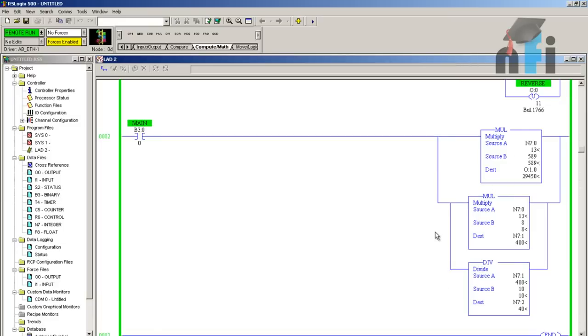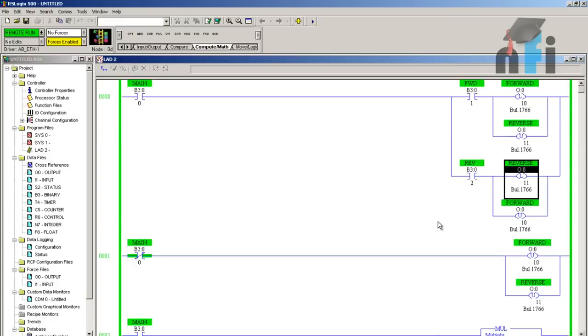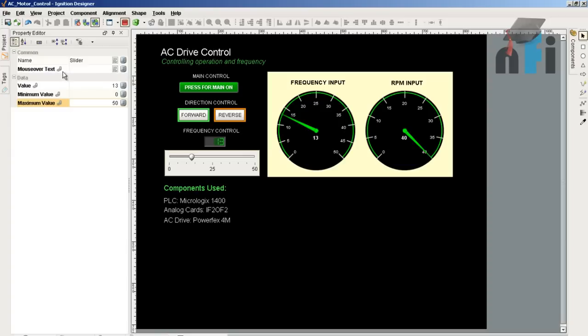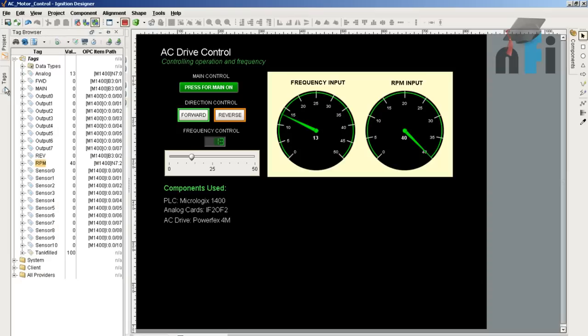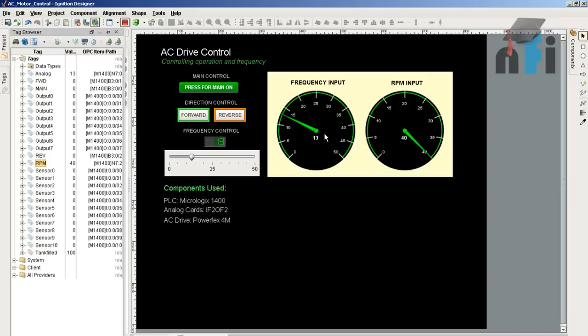The relevant tags we have made in this diagram: the reverse tag B3:0/2 which is given to reverse, the RPM tag N7:2 given here scaled to 0 to 40 RPM, and the frequency input which is analog N7:0. N7:0 is 0 to 50 hertz which we are giving by this slider.